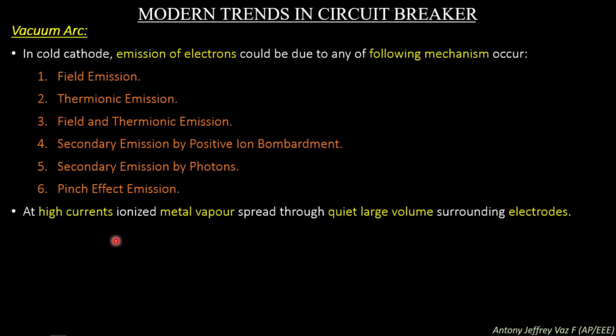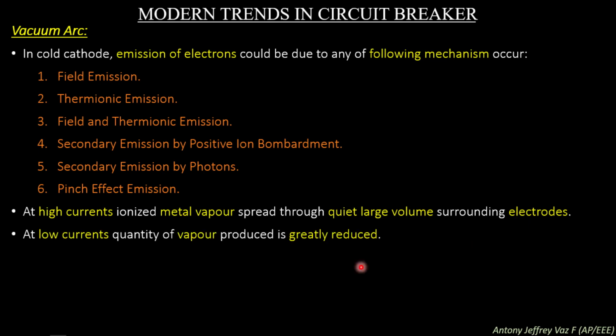At high currents, ionized metal vapor spreads through quite large volumes surrounding the electrodes. So, at this high current, the ionized metal vapors will spread through a large volume and surround the electrodes. At low currents, the quantity of vapor produced is greatly reduced.